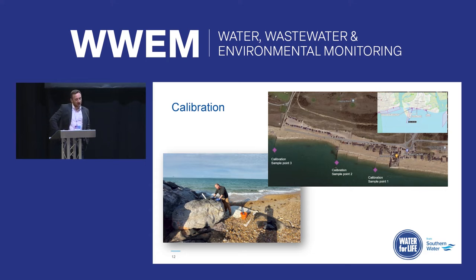So one of the things we must do is get a representative range of samples, corresponding lab samples and instrument measurements throughout the range that we might see. We're probably now up to about 40 samples, and we're yet to sample a high reading at any of these locations. So the water quality is very good at these locations when we've gone to sample them.